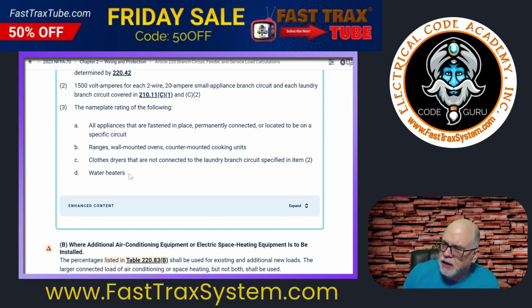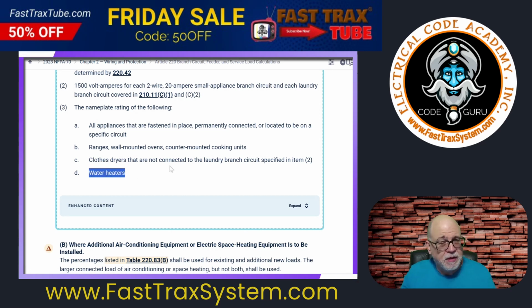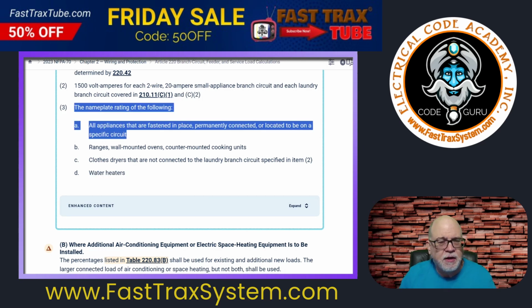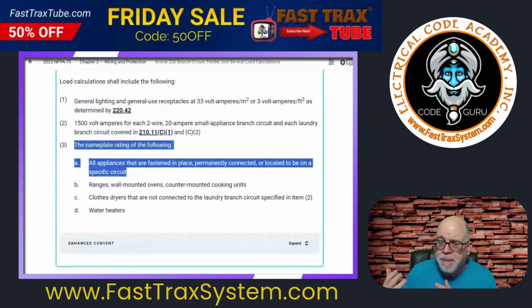And then, of course, any of the water heaters that you have. Okay. So what we're doing is we're simply taking the actual nameplates of all of these. We're adding all of this up. And remember, this is where people get confused. If there is existing heating and cooling, you go and you add that information as well into here. That all falls under 3, and more specifically 3A of the 2023 edition of the National Electrical Code. Straightforward, right? Makes sense. And that's what's going to determine whether or not you have the capacity. So basically, this is just like an optional method, that type of thing.